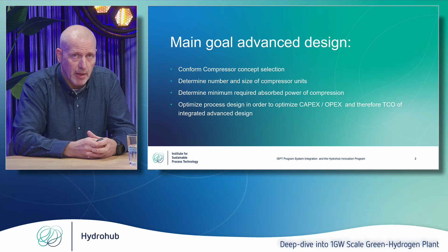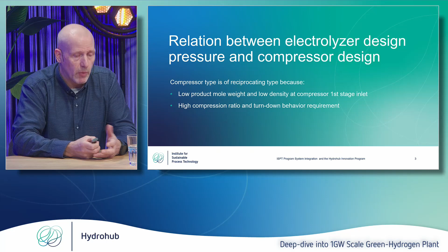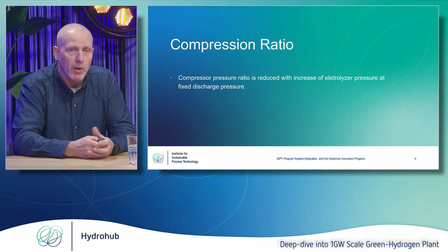There is obviously a very strong relation between the compressor design and the electrolyzer operating pressure, because the outlet pressure of the electrolyzer and the separation equipment is of course the inlet pressure of the first stage compressor. As hydrogen has a very low mole weight, and the density is very low at the first stage compressor inlet, the high compression ratio and the turndown behavior determine the type of compressor you will need. And we landed back at the reciprocating compressor type. Obviously, the compression ratio is reduced with an increase of the electrolyzer outlet pressure. So at a fixed discharge pressure, the ratio will drop. Next, the absorbed power: if you fix the mass flow through the whole compression system and reduce the compression ratio, the absorbed power will drop.